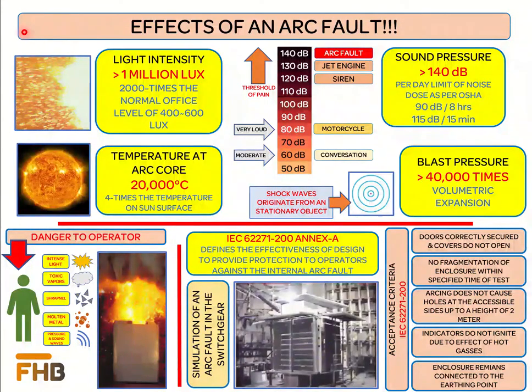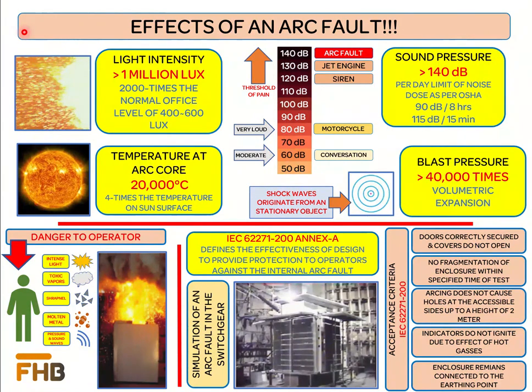It is common to use air as an insulation medium in medium voltage and low voltage switchgears. There are various reasons to use air as an insulating medium: it is not harmful to the environment, it restores itself after breakdown, and above all, it is free. However, in the presence of impurities, air becomes conductive at higher temperatures — ranges above 1000 degrees centigrade. Once the arc is ignited within the switchgear, the surrounding air will get ionized, and the arc will continue to burn at very high temperature until it is interrupted.